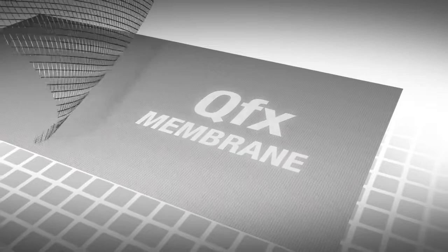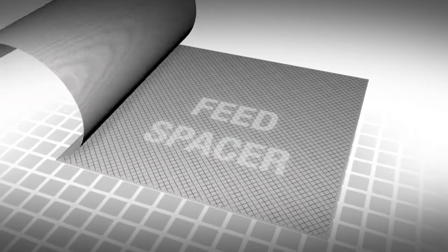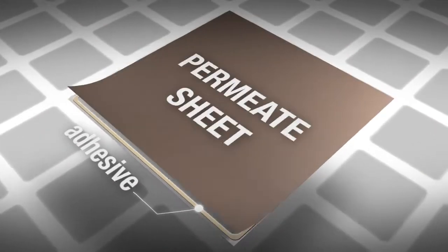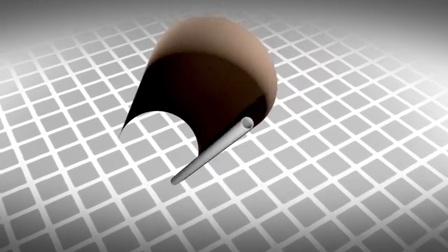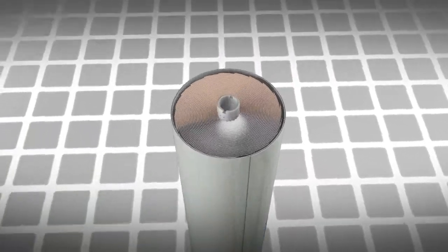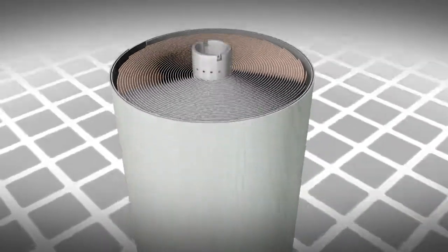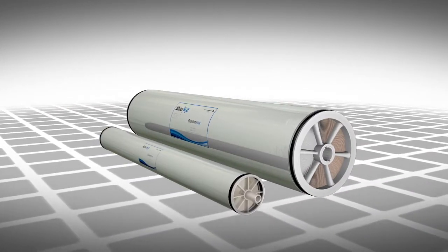Sheets of thin-film nanocomposite membrane are folded, feed spacer material is inserted, and adhesive is applied with precision along the edges of the membrane leaves. These leaves, sandwiched between layers of permeate sheets, are spirally wound around a permeate tube that collects the product water. Each element is wet-tested for flux and rejection to ensure that it meets exacting specifications and the highest quality standards.